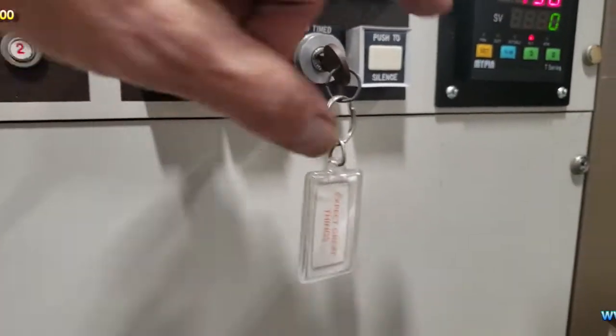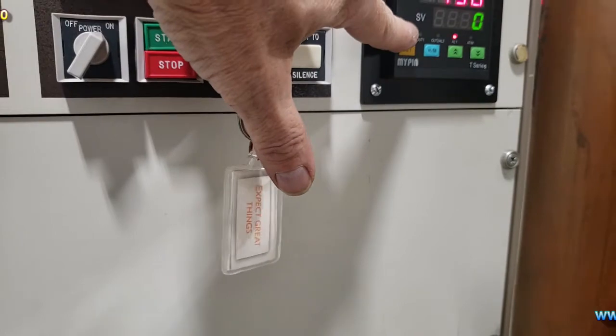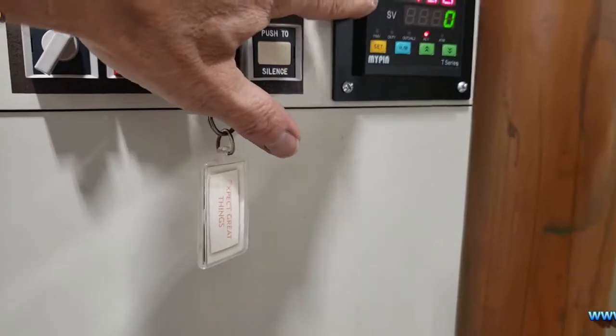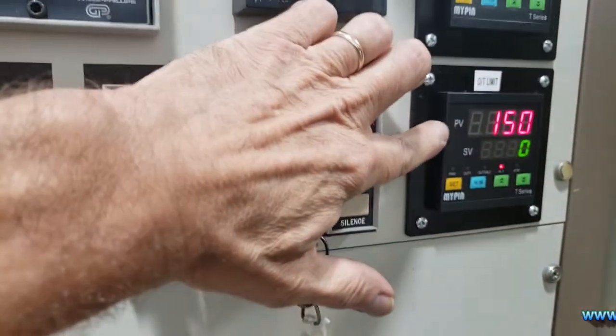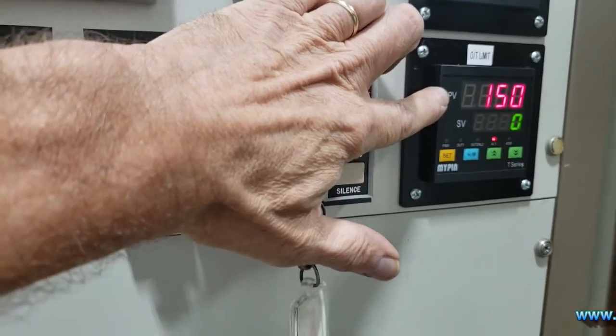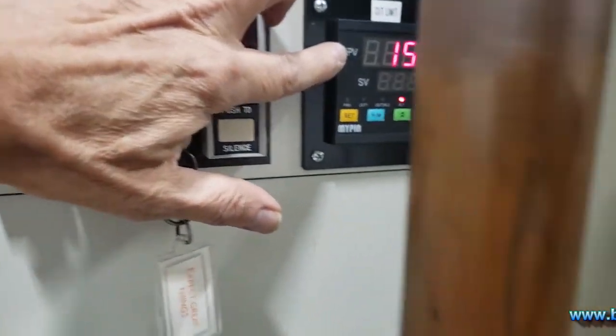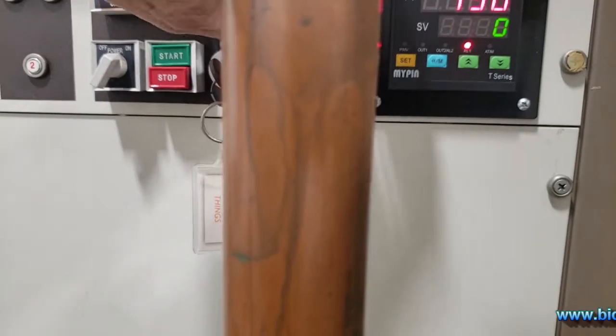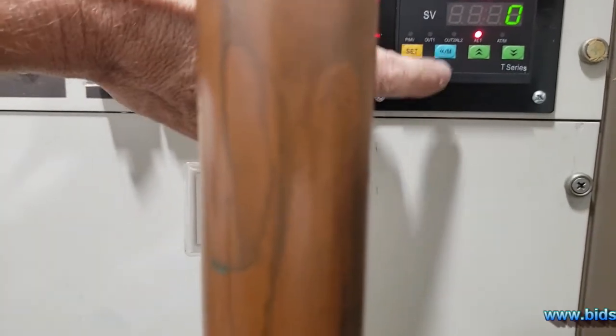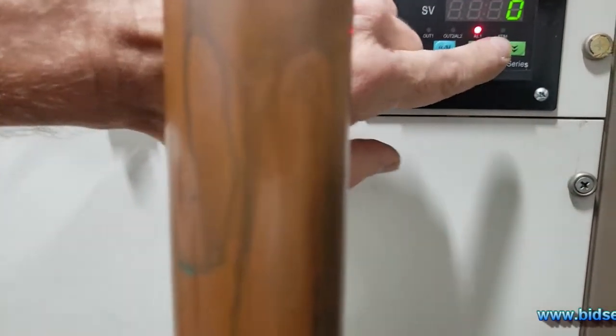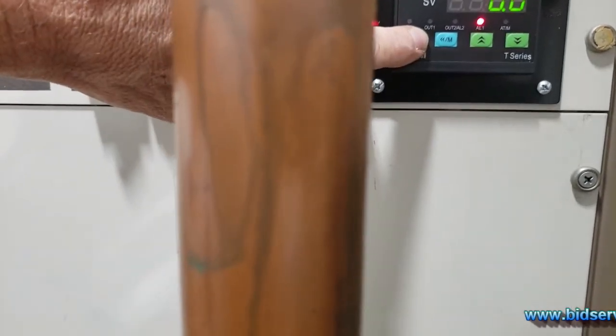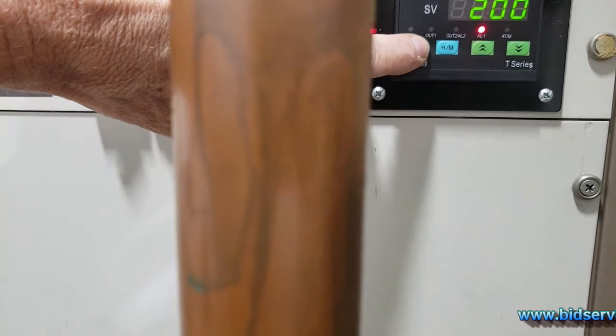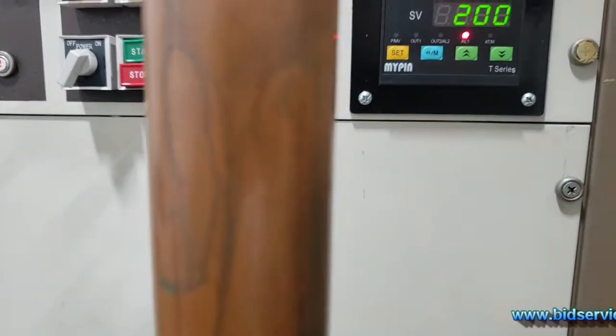The lower one is just a redundant alarm. There is no set value on this. What it is reading is its own, it has its own independent thermocouple attached to it. It's calibrated so they both read the same temperature, but they are two independent thermocouples. Just reading 150 Celsius at the time. There's no set value. It has no control output on it, but it does have the alarm. And again, to see what that alarm's set at, we'll go ahead and press and hold set. And you see alarm 1 here set at 200.